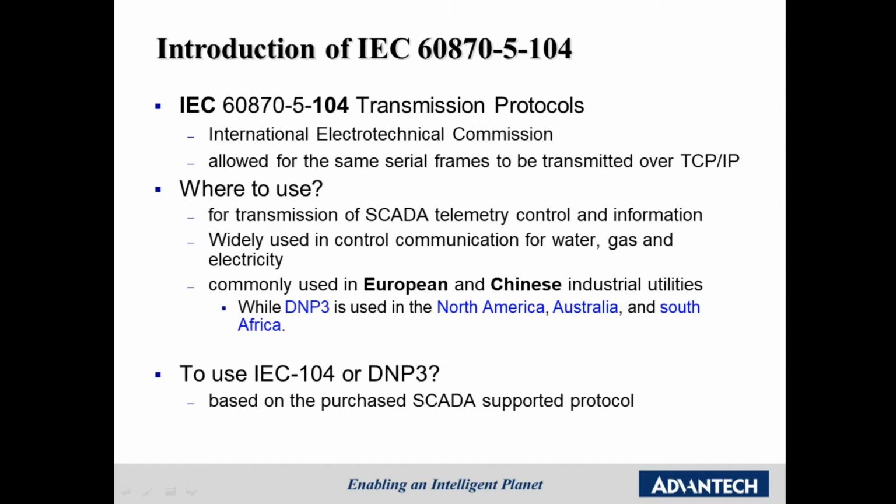For instance, IEC 104 does not support short timestamps. The length of the various address elements is set to defined maximum values. But in practice, vendors very often combine the IEC 101 application layer with the IEC 104 transport profile without paying attention to these restrictions. This might then lead to problems if a device strictly applies the standard.